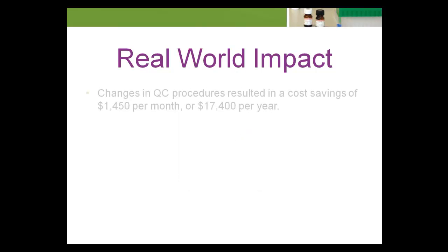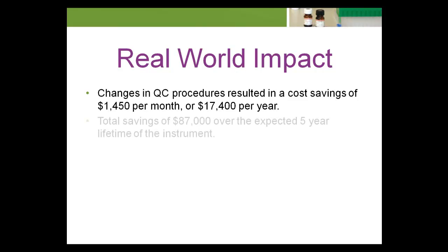These changes resulted in a dramatic drop of false rejections in the laboratory, with significant savings due to the savings of retesting. It should also be pointed out that the quality of the problem analytes increased due to the tighter controls that were placed on them. The general impact of quality control design is to increase the scrutiny of tests that are in danger of being out of specification, and to reduce scrutiny of tests that don't. This allows a laboratory to become more efficient while increasing the quality of its testing. This should be the goal of all of us.